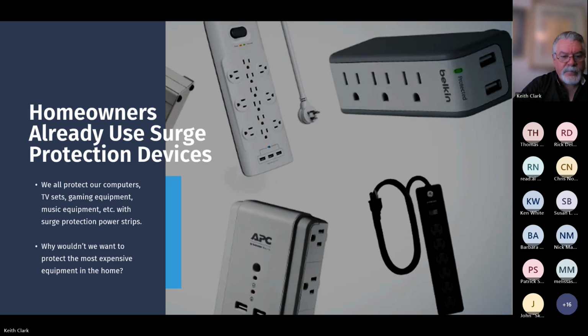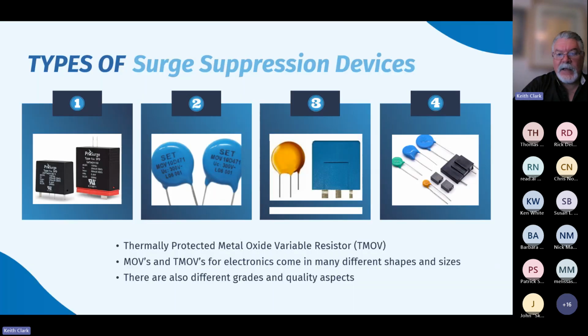But we protect that equipment. Why wouldn't we protect the most expensive piece of equipment in the house, which is your HVAC system? What you're going to see inside those power strips are these little disc type MOVs. When they fail, they typically fail catastrophically. And we use a TMOV, which is a thermally protected metal oxide variable resistor. That's a fancy term, but you can impress your friends if you commit it to memory. But TMOVs are the best type of device for handling these transient surges.